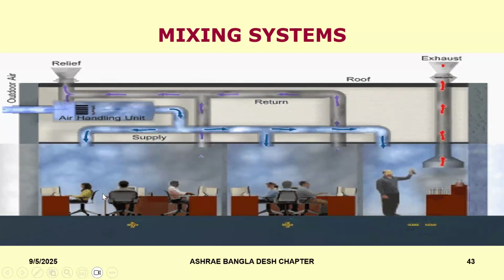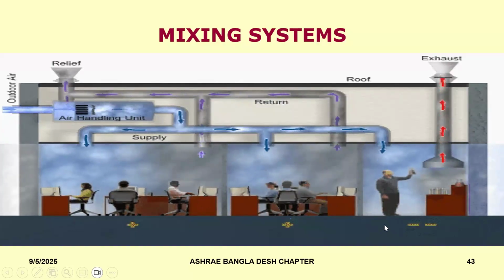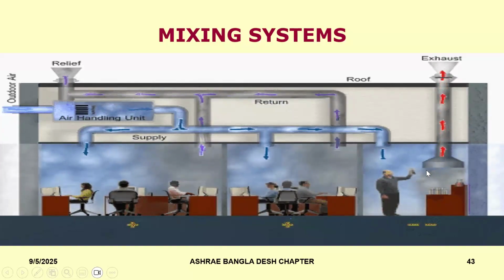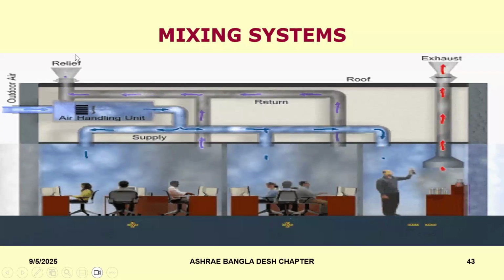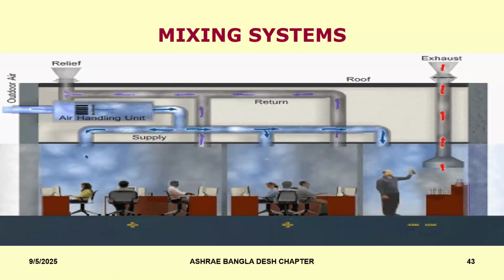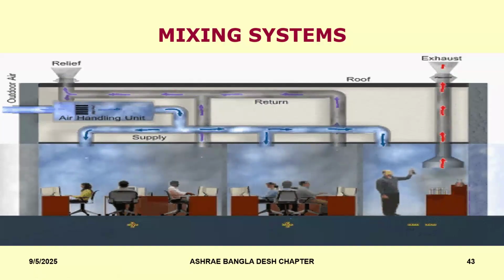So this outdoor air is based on number of people, square foot per person, etc., plus whatever is going out from here and here, so that proper air balance is maintained. This is really how a full-blown mixing air system would work, no matter how large the space is.